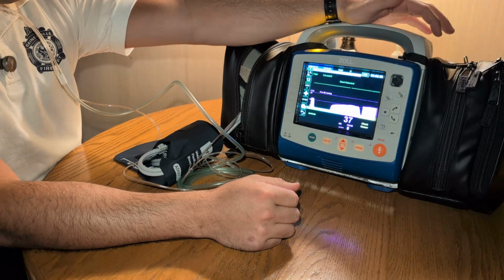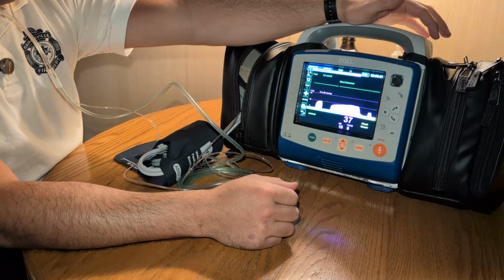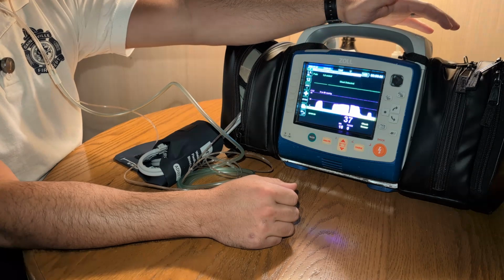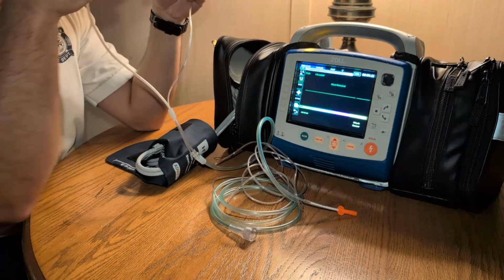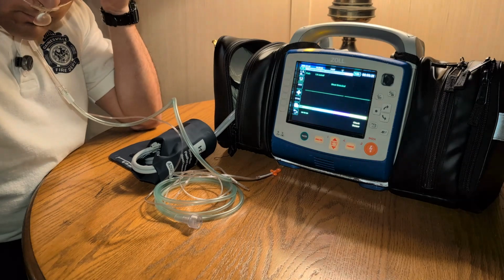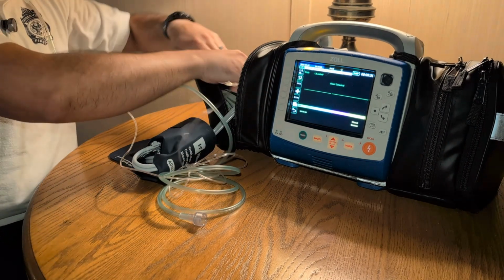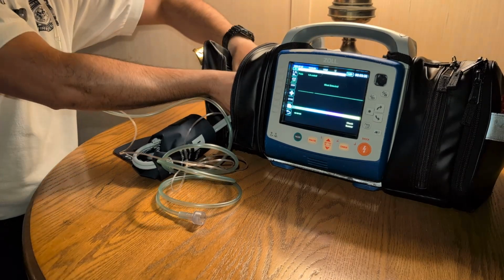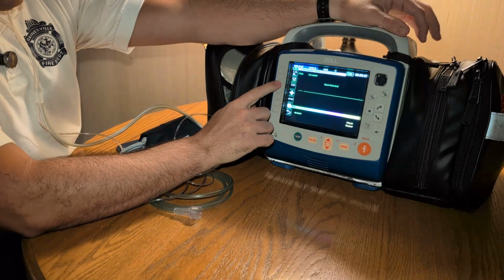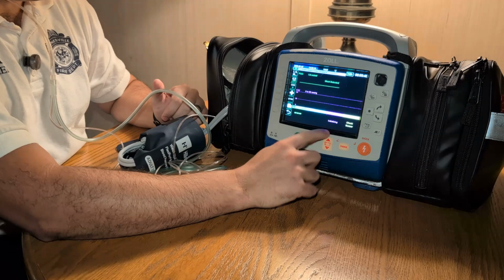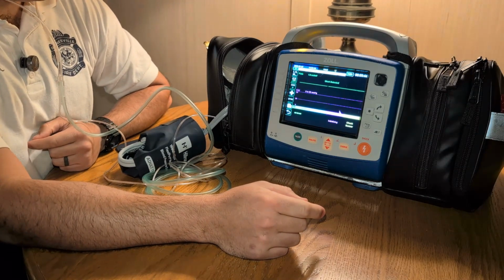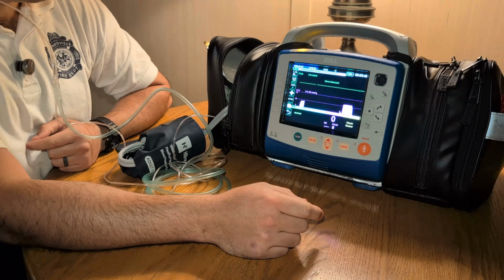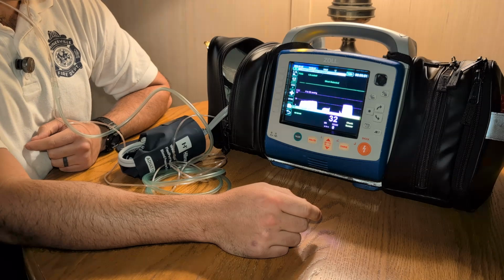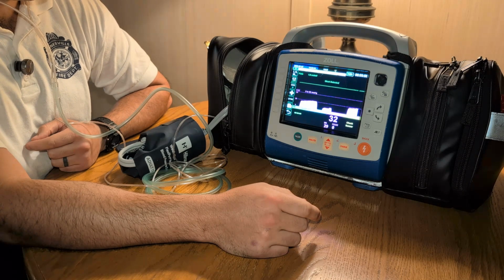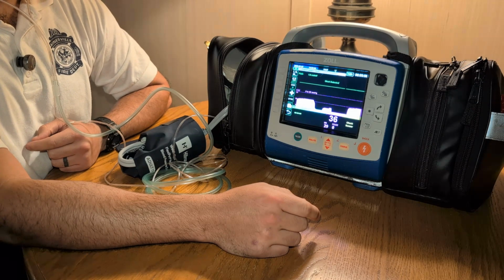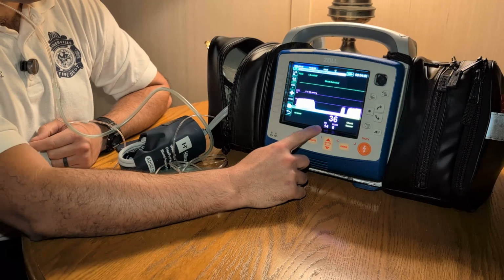We're getting a reading of 37. Breath rate of 15, right across the board. Now, I'm going to put the cannula on first and breathe. All right. Plug this guy in while the cannula is applied. Then hit CO2. It's going to initialize while I'm breathing into this cannula. And we're right back where we started. 36, breath rate of 14.